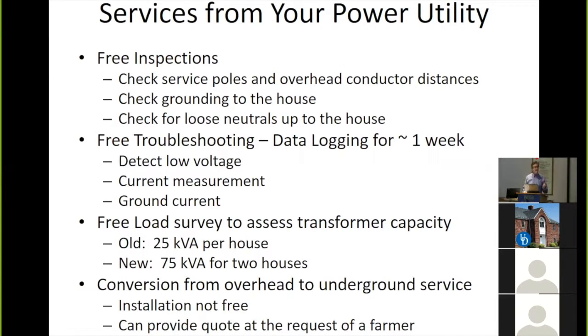The other thing utilities will do, and I know the co-op does this because I've worked with them on this, is free troubleshooting. They'll come out and put a little computer, what we call a data logger, on your farm, and they'll actually watch the voltage and the electrical current you're using as a means to see if there's a problem, or if you already know there's a problem, what the problem is.